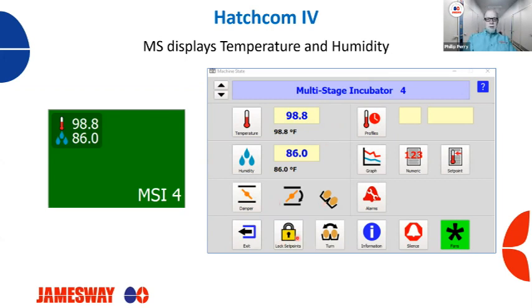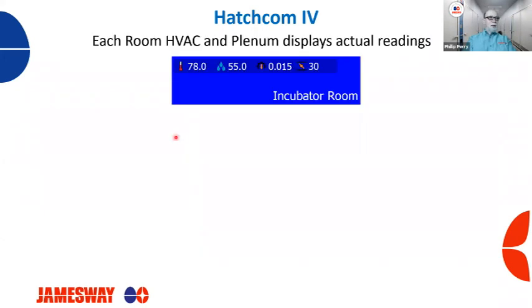You can also lock your set points from here and just monitor the alarms from here. So just some of the features that Hatchcom 4 has for the multi-stage. Next, we're going to show the room heating, ventilation, air conditioning, and the plenum displays actual readings. So if you have a Guardian system now or a Guardian panel, you can link it to your Hatchcom and you would be able to monitor this from your office or wherever you have access to your Hatchcom.